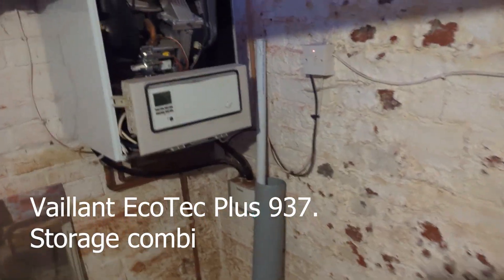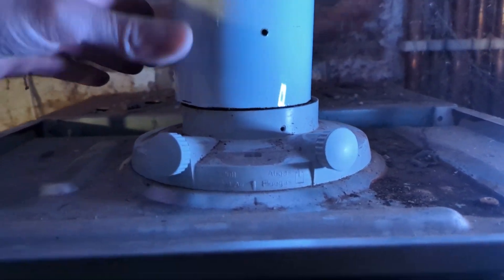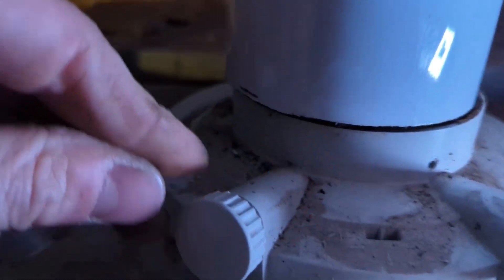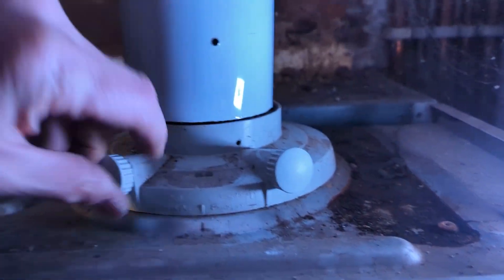Hi, I was initially a little bit stuck on this job. Came to replace the seal on the top of the heat exchanger due to the flue integrity test failing. As you can see, the flue adapter — there's no screws holding it on top of the heat exchanger, and the last few times I've ever done this job that always has. So I could not work out how this flue adapter came off.